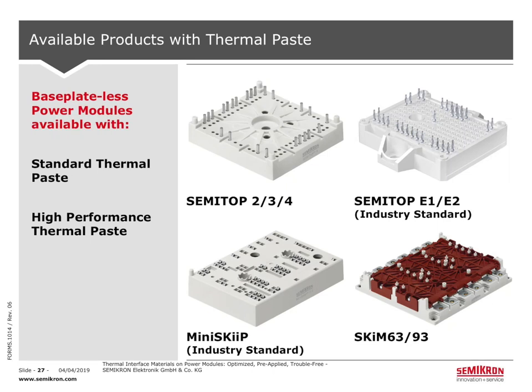The mounting process is very fast with one or two screws. Basically you mount the PCB on top of the module, and you mount everything together on the heatsink. That is done very fast and is therefore perfectly designed for high volume production. Available topologies are the standard topologies in motor drives: converter, inverter, brake power modules, where you have a rectifier, a brake chopper and an inverter stage combined in one power module. You have six-packs, and rectifiers with our own chips, as mentioned in the beginning. This makes it the perfect scalable motor drive platform from 1 to 90 kilowatt.